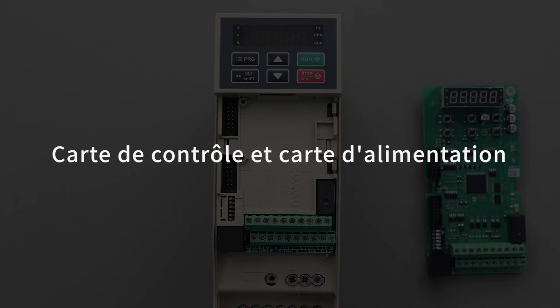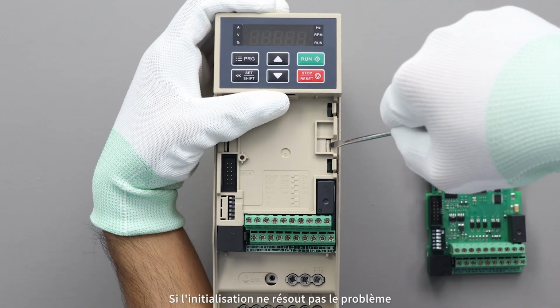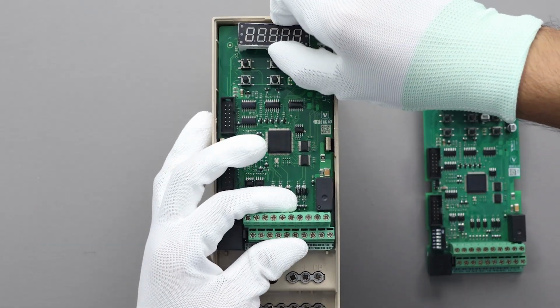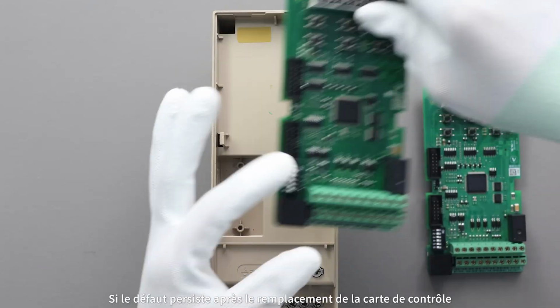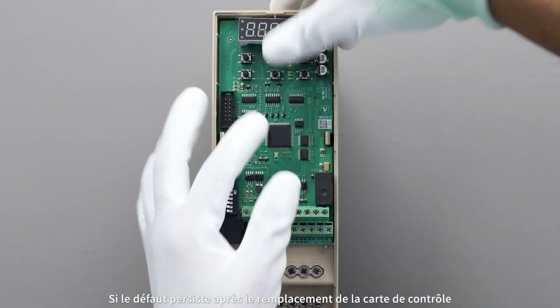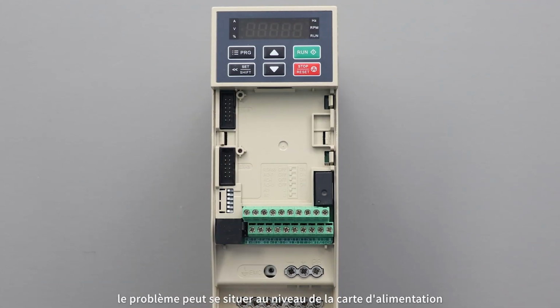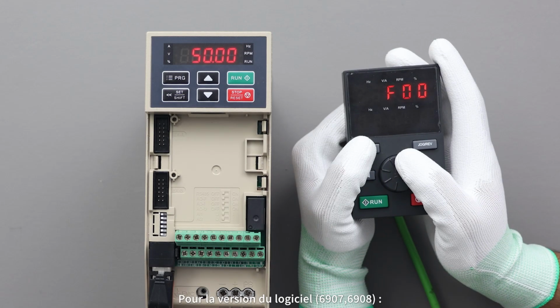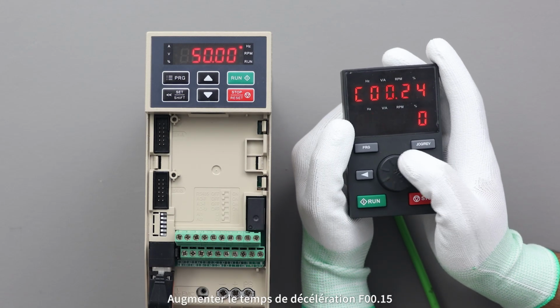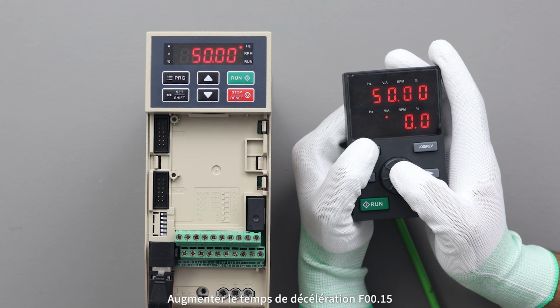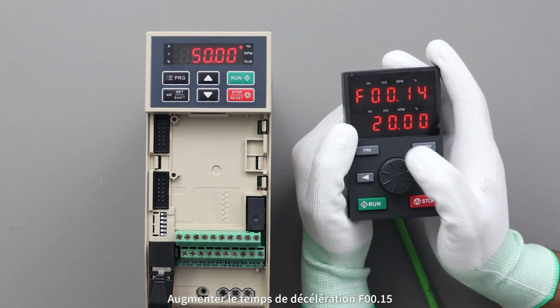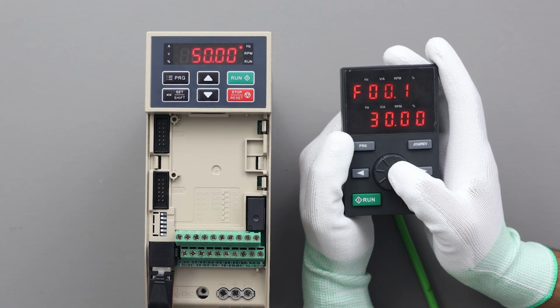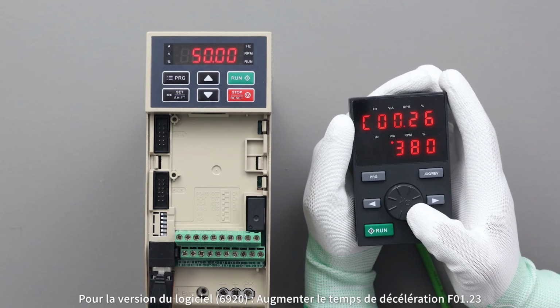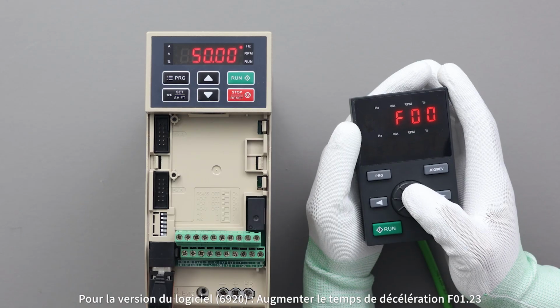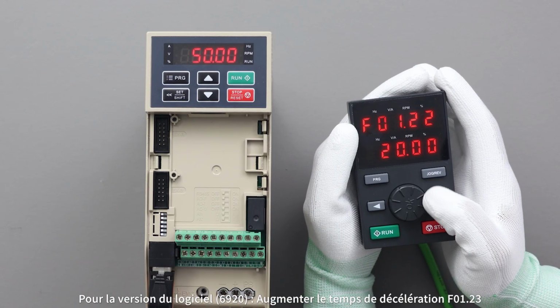Control board, power board. If initialization does not resolve the issue, replace the control board. If the fault continues after replacing the control board, the problem may be with the power board. For software version 6907 and 6908, increase deceleration time F00.15. For software version 6920, increase deceleration time F01.23.